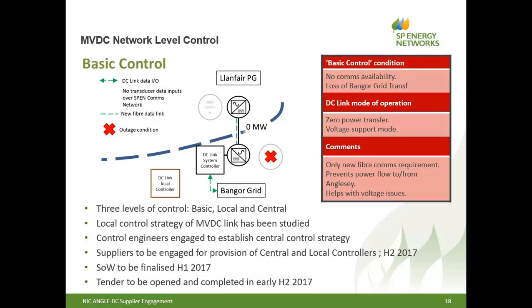What we then really need to do is shut the link down from a power transfer point of view, but we may gain some benefit through a voltage support mode. That will be something that doesn't rely on telecoms and communication systems, and it can be a hardwired setup back at the local substation. So that gives us some assurance that if something does go drastically wrong, we can switch straight into that.